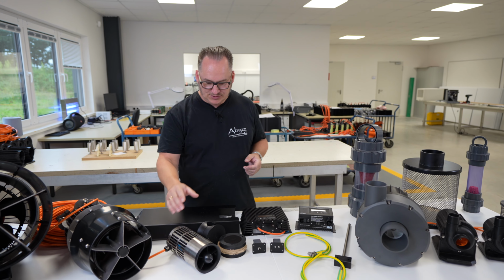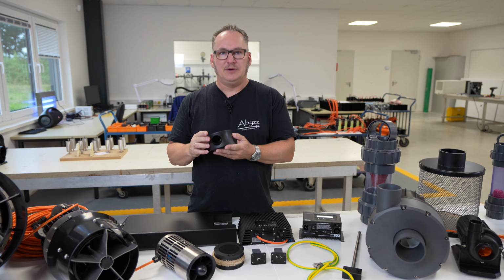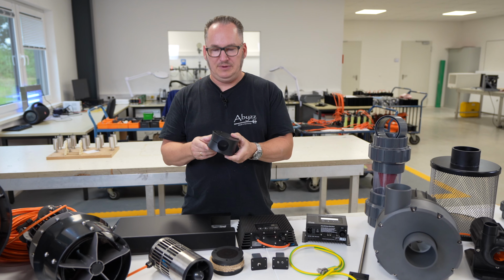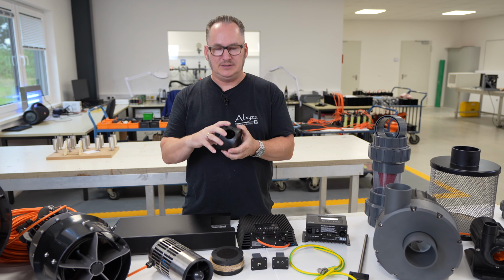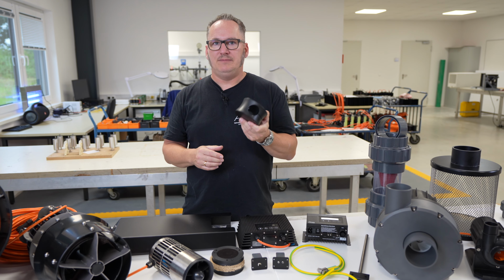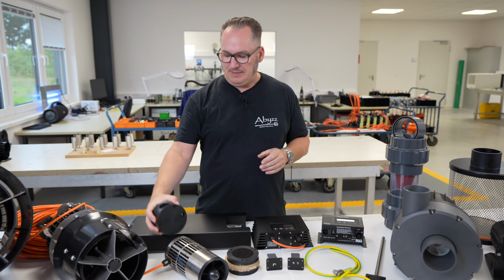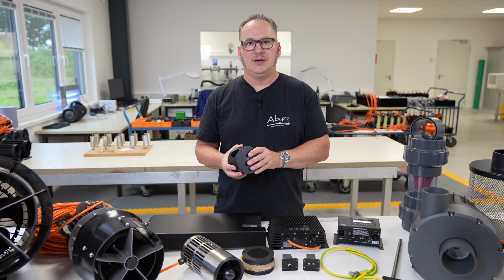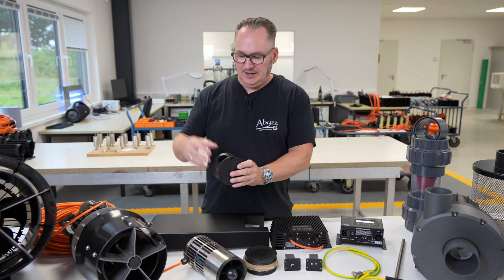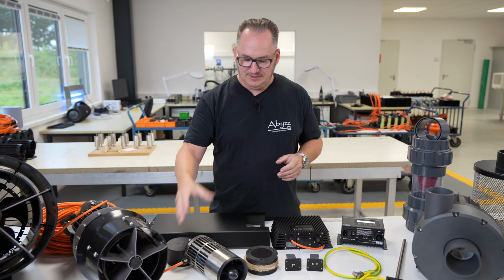For the small one, I just want to cover the easiest mounting option, which would be for a PVC pipe. You can use a standard DN PVC pipe available in metric and imperial. This connects to the pump on the rear with 3 titanium screws, and then you can directly mount your PVC pipe and put the pump on it.